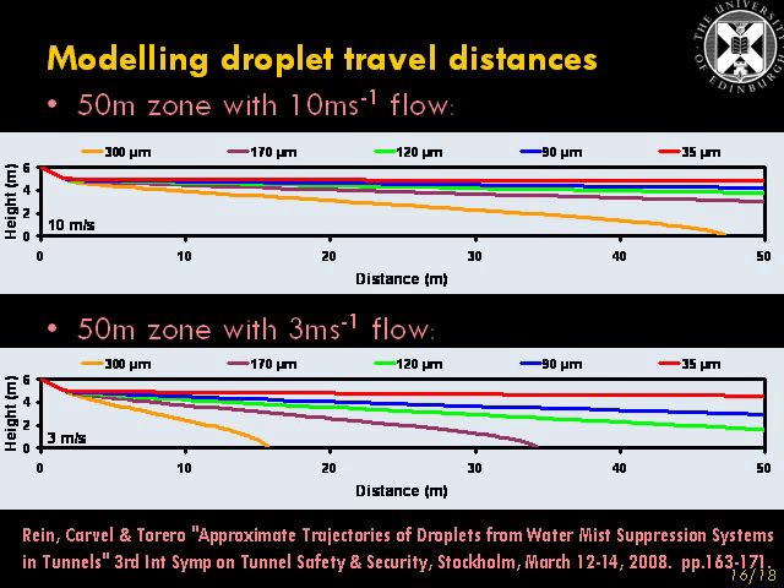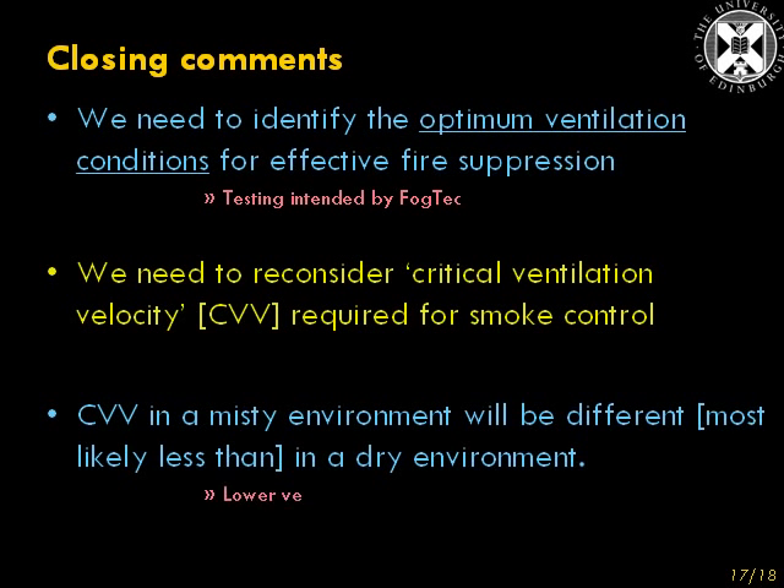Those results were published at the Third International Symposium on Tunnel Safety and Security in Stockholm 2008, and can be downloaded from my website, www.tunnelfiresafety.co.uk. So actually, we don't need to think about whether suppression systems can work at very high ventilation conditions — what we need to identify are the optimum ventilation conditions for effective fire suppression. I believe that some testing is intended by the water mist company FogTec to look at that very issue.